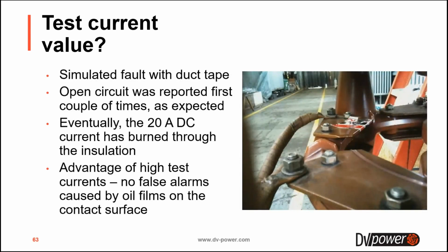And that we also simulated in the lab by putting a duct tape on one of the stationary contacts. So the first few times when we recorded, we got an open circuit because there was a duct tape and we could not establish the current. The current would drop to 0, but after a few times we used 20 amps DC, that current burned the insulation, as you can see here on this photo. So this is the advantage of high currents. High current can burn that insulation, because that insulation can give you a false alarm that something is wrong with the tap changer, that you have an open circuit and so on, but maybe it's just some thin layer of insulation that needs to be cleaned and everything can be good.